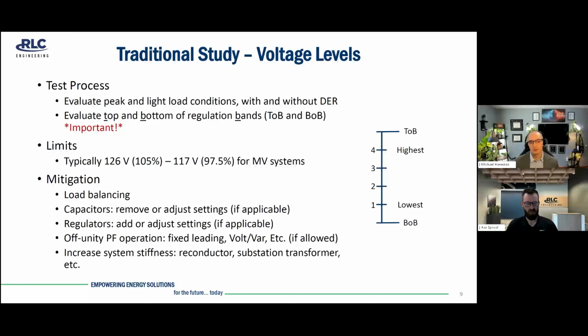Now, as far as the limits, those are pretty typical. 105% high voltage is common, 97.5% for low voltage is a common limit threshold for medium voltage systems. If you want to mitigate, load balancing is a good place to start if you have a lot of imbalance within the system that the DER is attempting to interconnect to. You can adjust or remove capacitors potentially, add or adjust regulator settings, use off unity power factor, so fixed leading, volt-var, etc., or increase system stiffness. So that's the reconductoring or substation transformer upgrades.